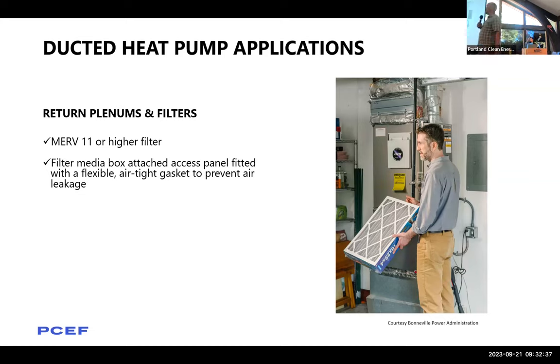That second line there, the second check it anyway. Make sure that you're getting the right size filter. I think I'm speaking more to the grantees in the room than the installers, because to my knowledge, you at the grantee level are going to have the more ongoing relationship with these homeowners and tenants than the contractor. When you start replacing these filters, if you replace them with the wrong size and you get a bunch of air bypassing, that filter is not doing anything for you. So this is a key component on the homeowner education side, ongoing maintenance, whatever your program looks like. Make sure the right size filter gets in there and that the lid seals tight enough that you don't get blow by. That's what it's called, air bypassing the filter assembly itself.